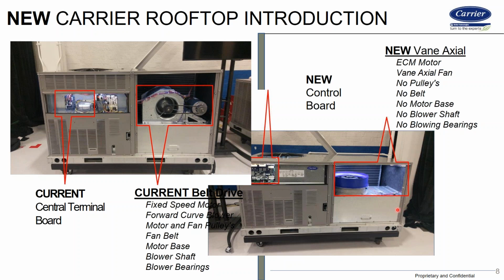The first one may take you 20 minutes or half an hour. You know, you've got to think it through. But once you do one, it's a breeze. It literally takes 10 minutes. So that's going to correct the problem of the unit tripping on limit and completely flushing the IGC board of all of its faults.